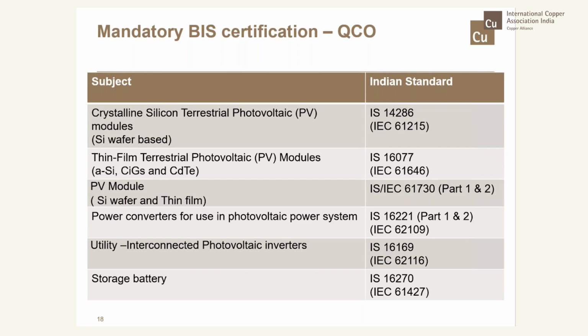Then in this slide, I have projected the mandatory implementation of the Indian Standard quality control order that has been issued by MNRE, the nodal ministry in India. This list of standards was made mandatory since 2017, but the dates for implementation have been extended a number of times. Check the website of BIS or MNRE to get the latest date. These are: crystalline silicon PV modules, IS 14286; thin film modules, 16077; PV modules thin film type, IS IEC 61730; power converter, 16221; utility interconnected photovoltaic inverter, IS 16169; then storage battery, 16270. These all come under mandatory BIS certification. So all the products placed in the Indian market have to have BIS certification compulsorily.